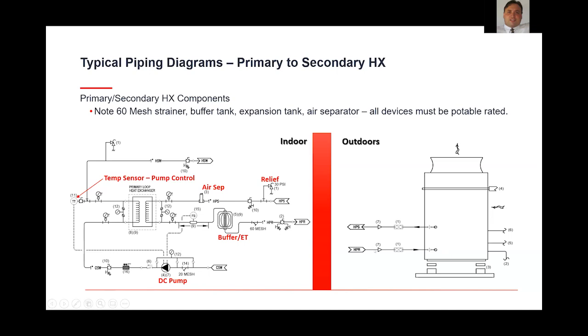Although there may be allowances for glycol, that's something Mitsubishi's looking at allowing at least up to 30% propylene. But depending on climate, it's probably a good practice to incorporate both glycol and heat trace, depending on what concentration you can get into that loop, especially for burst protection. So again, 2 pipe sizes, 2 pipes from the outdoor unit to your indoor location, heat traced, typically with glycol.